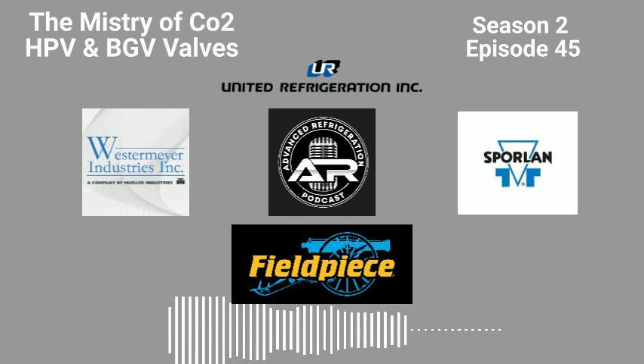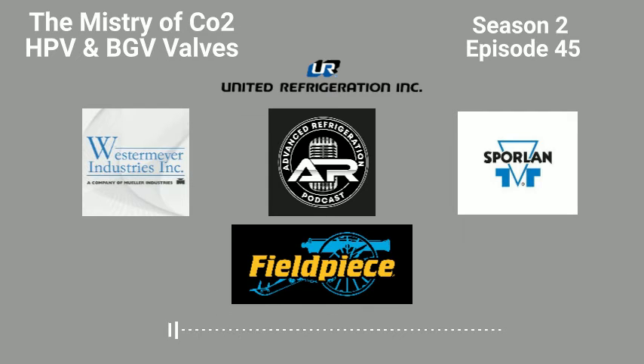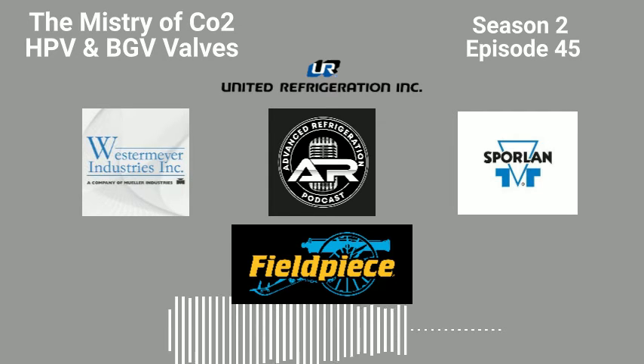So this controller has to have a flash tank pressure transducer, a drop leg transducer, and a drop leg temp sensor to work. It needs these three things, basic bare bones, bare minimum for this thing to work. So it's taking those readings, and then it's constantly running this algorithm to maintain this tank pressure and subcooling, and efficient gas cooler pressure and temperature. So it's constantly walking this fine line. When it's cold out, you run like a freight train. I mean, these racks thrive when it's like 0 degrees outside.